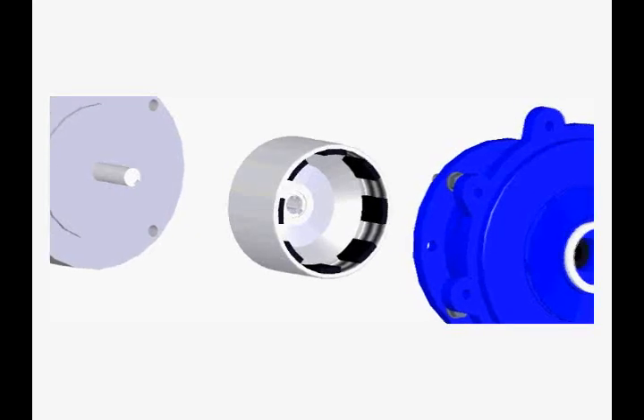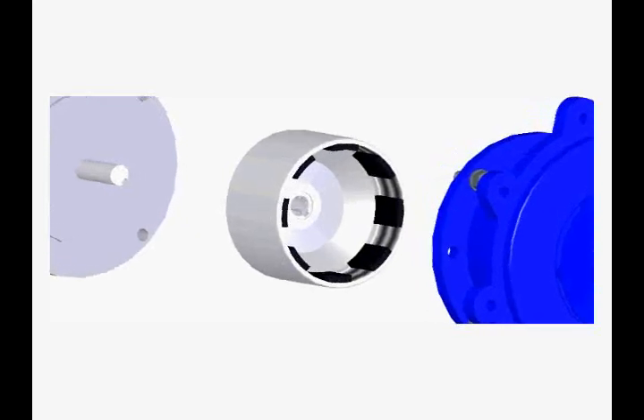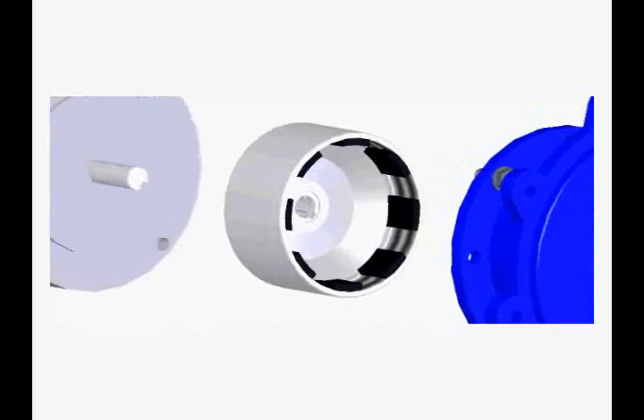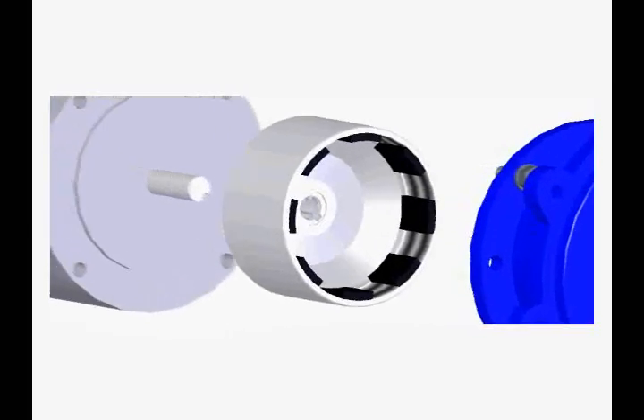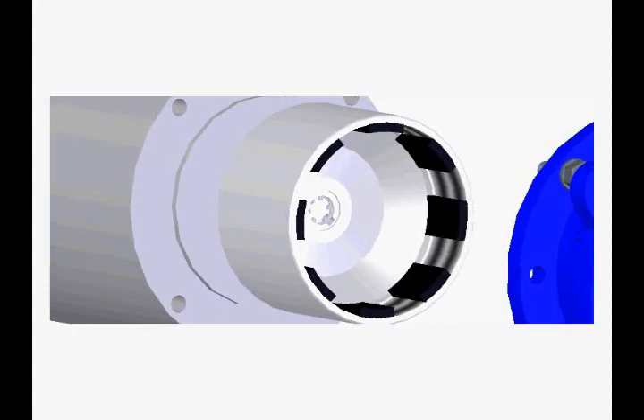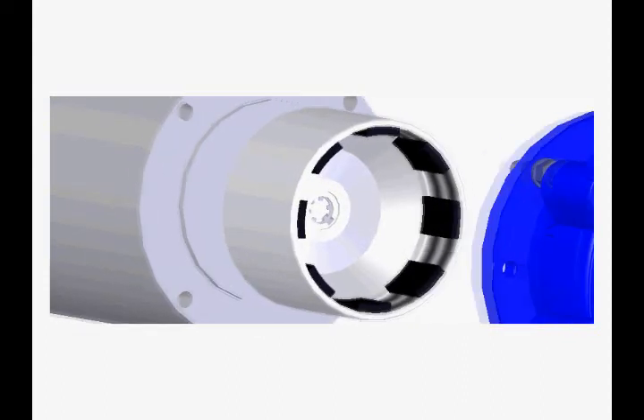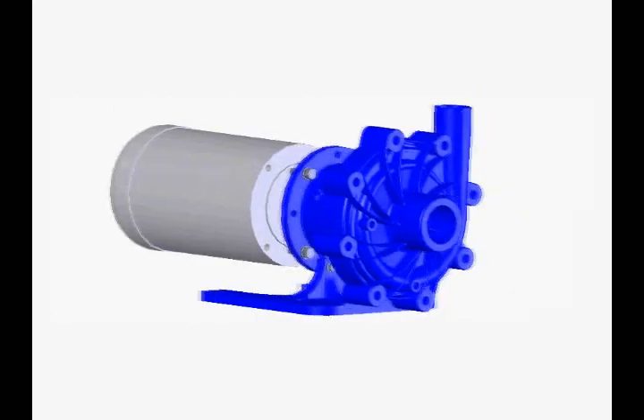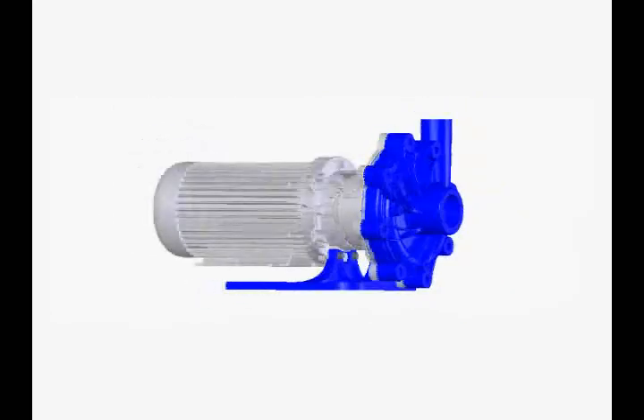The DB Series unique Easy Set Outer Drive feature makes installing the pump on a motor quick and easy. Simply slide the outer drive onto the motor shaft until it reaches a built-in stop. The Easy Set Outer Drive perfectly aligns the magnets without any mechanical adjustments or measurements.